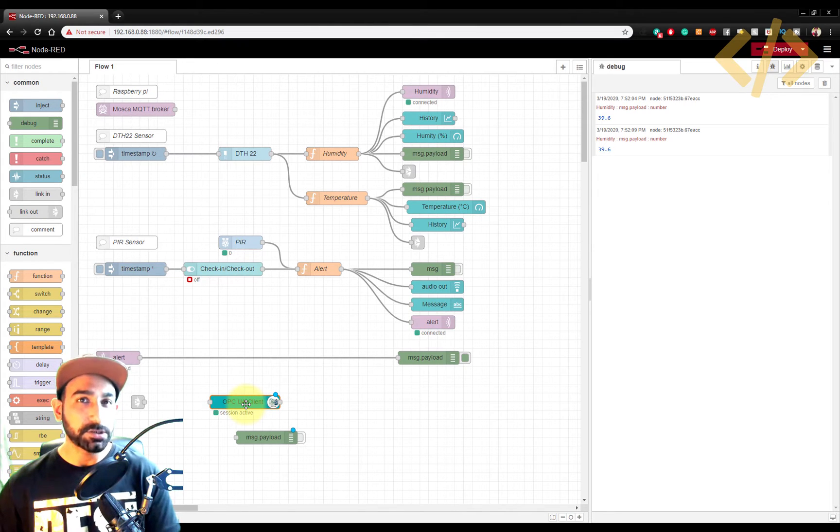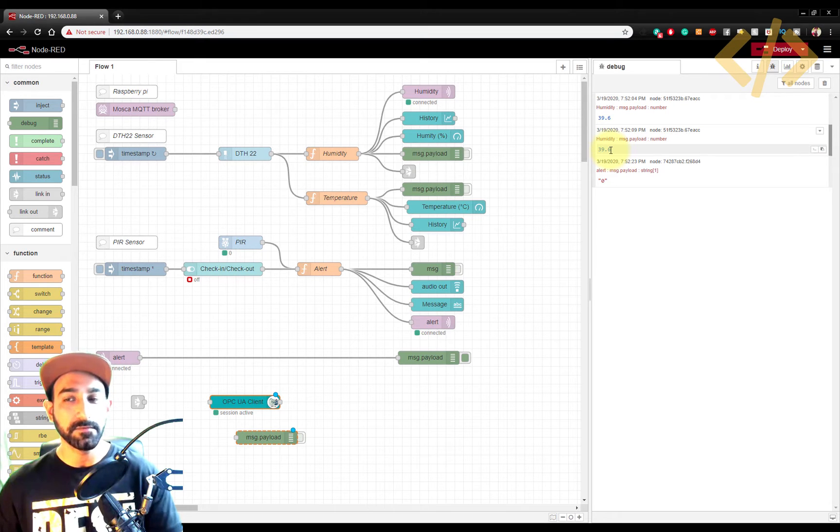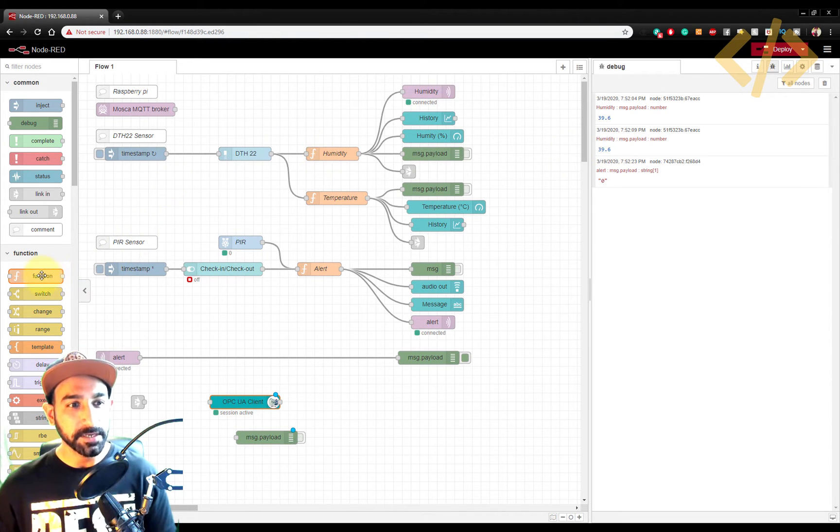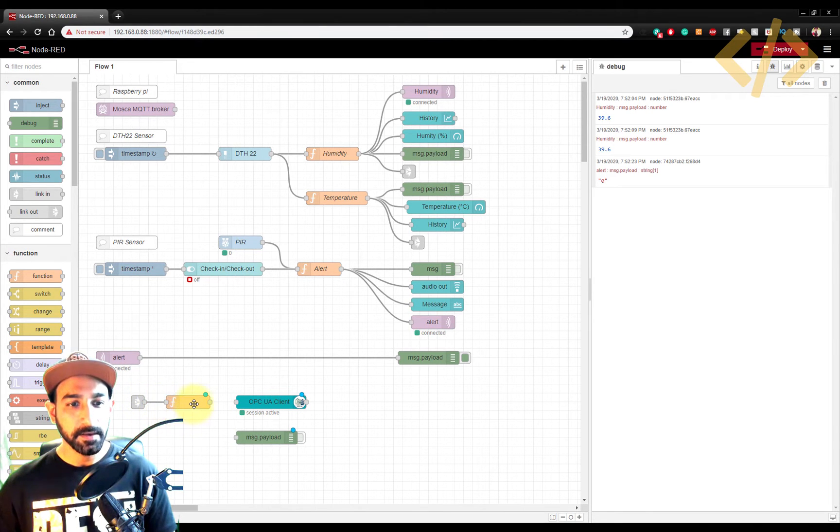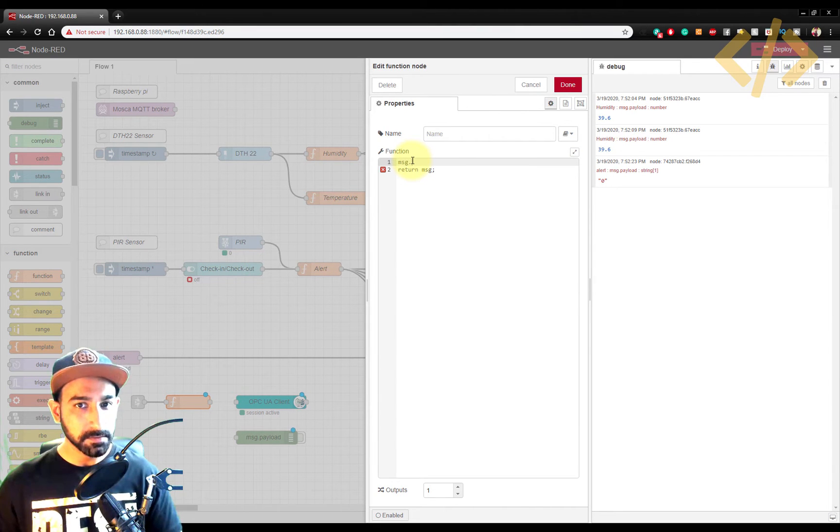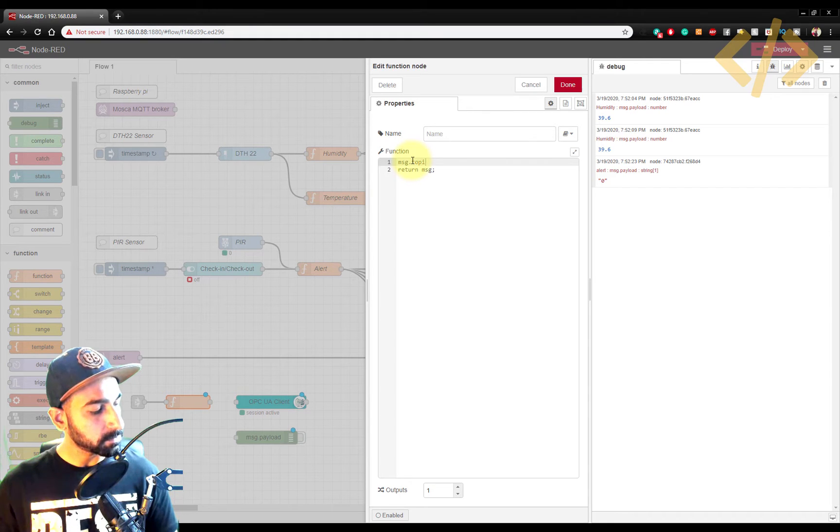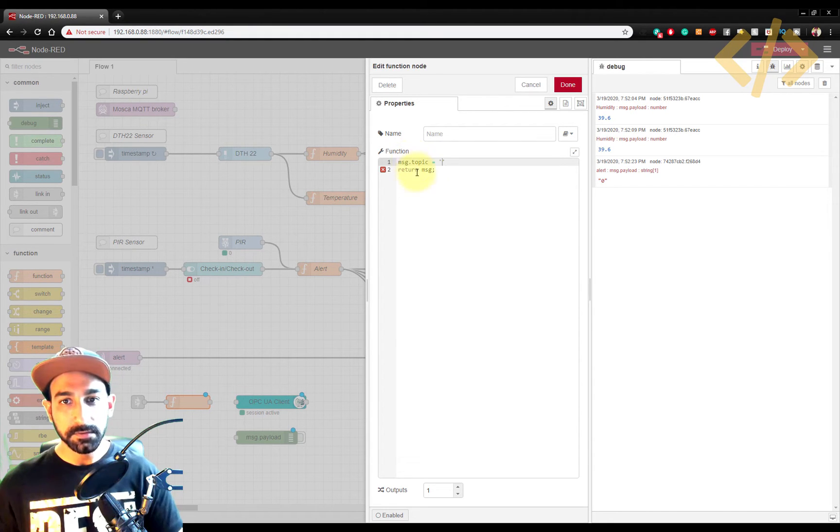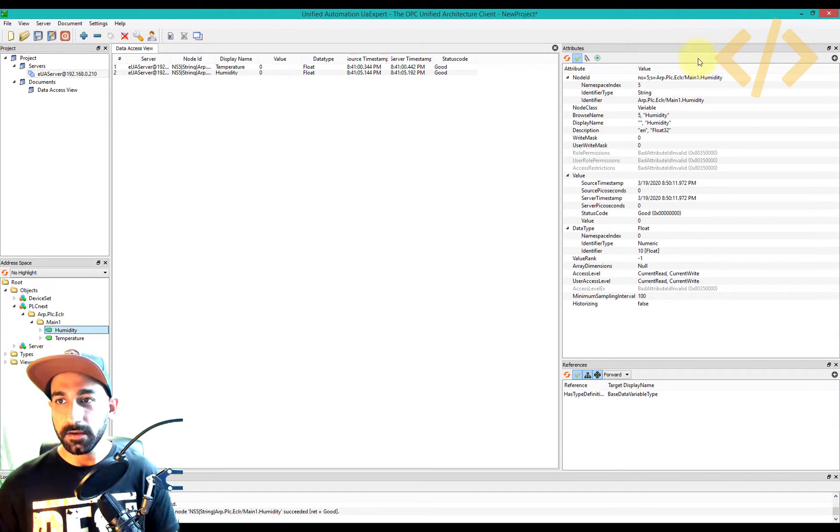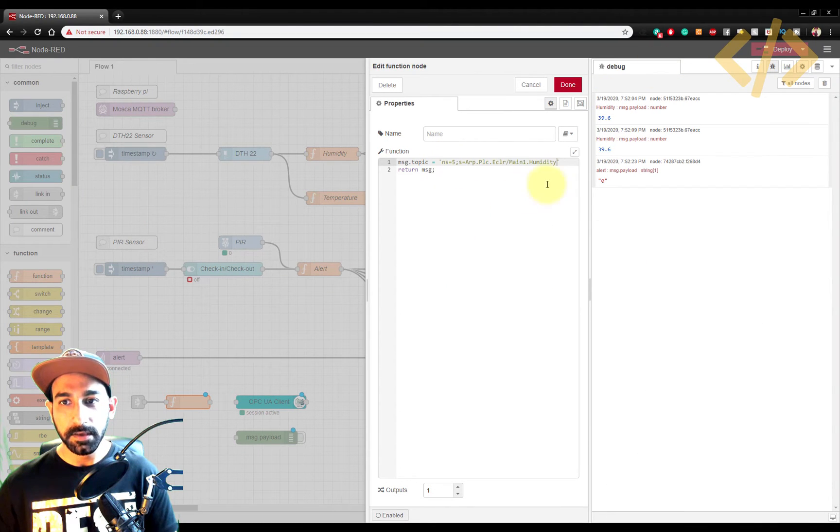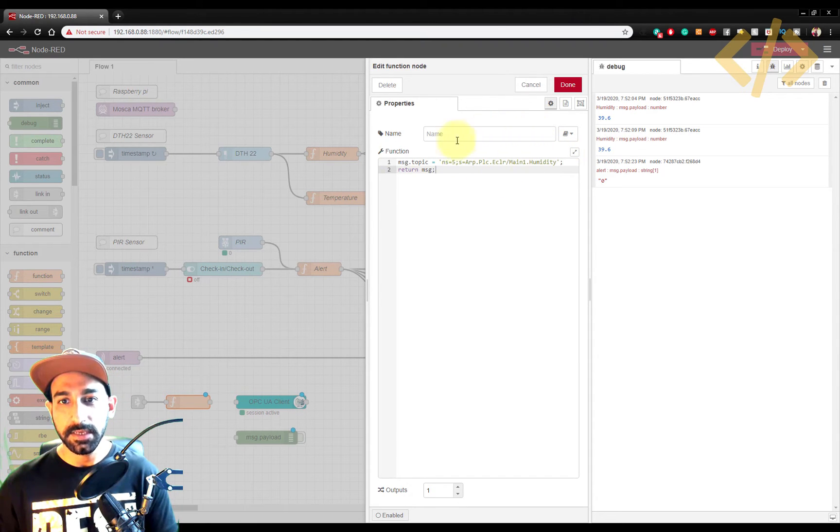So I will just delete it for the moment. Now to write to the OPC value, what do you need? You need a payload and you need a topic. The topic is the address of the tag and payload is this humidity. So I have this payload, but I need a topic. So where should this value go? That's the topic. So I have to take a function here where I define the topic. So I connect this link here. And inside the function, I will write message dot topic is equivalent to two commas. And inside this, I will put the address, which will come from here. So this is humidity. Copy value, put it here, paste, and a semicolon.